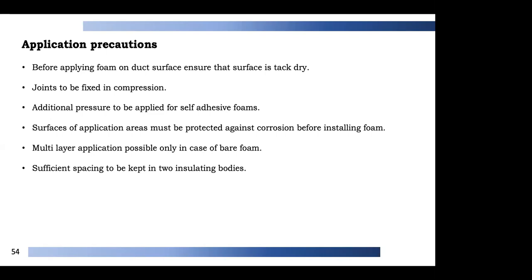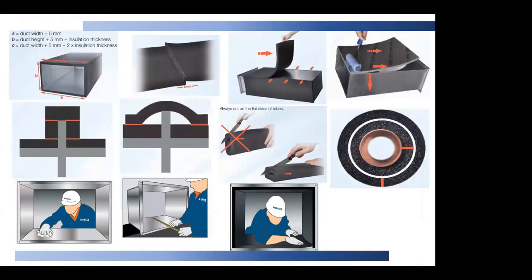Adhesive should be applied thinly and evenly on duct surfaces as well as the foam. Before applying foam on duct surface, ensure the surface is tack dry — after applying adhesive, keep the surfaces open to atmosphere for a few seconds before pressing down. Joints should be fixed in compression. For self-adhesive foams, apply additional pressure to ensure proper adhesion to the ducting or pipe area. Protect surfaces against corrosion before installing foam. Multi-layer application is possible only with bare foams — ensure insulation is not coated with lamination before adding further layers. Maintain sufficient spacing between insulating bodies.